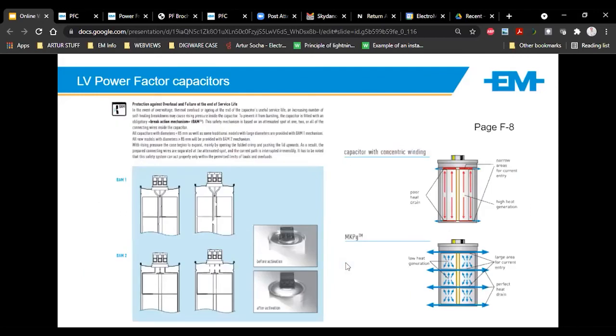The protection system, they call it the BAM. As a capacitor sees too many voltages or issues or overloads, it does build up pressure internally, and instead of just rupturing, it will release itself and disconnect itself from the network. A typical capacitor should have over 150,000 hours worth of life. It's all dependent on how well you're protecting that capacitor. If you don't put line reactors on and you've got a lot of harmonics, your capacitors will not last. They will blow out, they will fail.